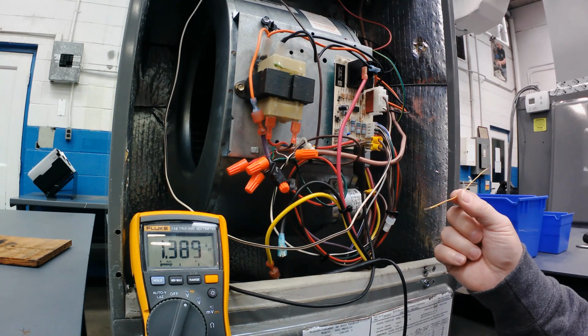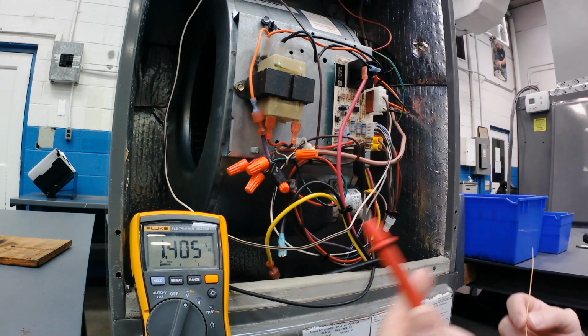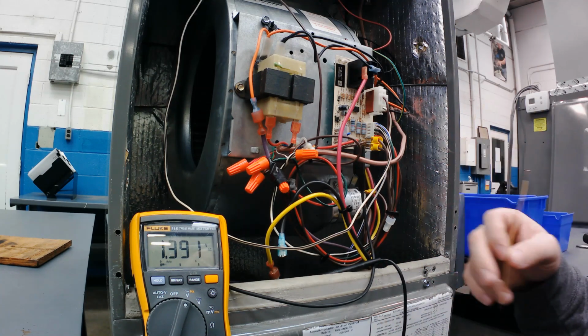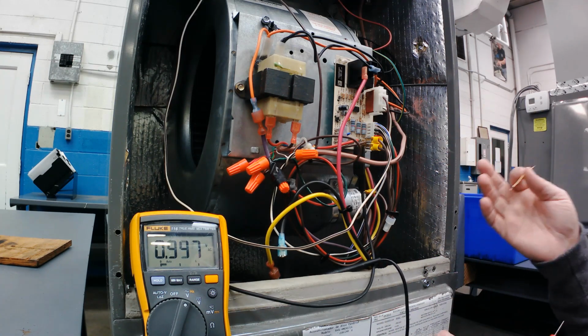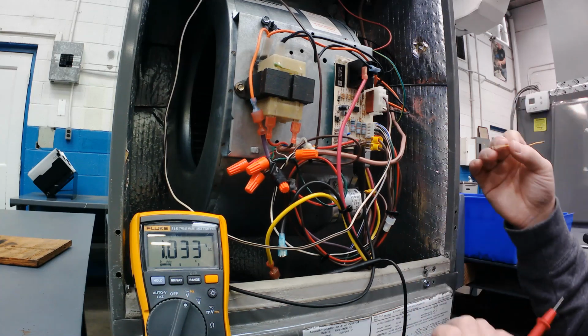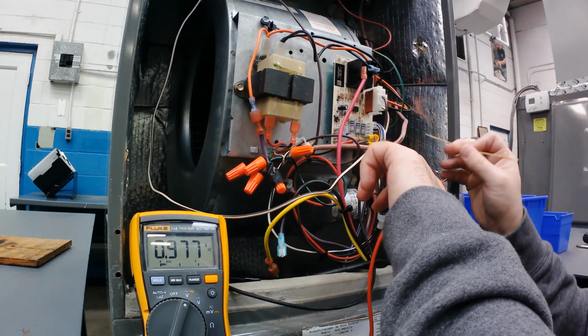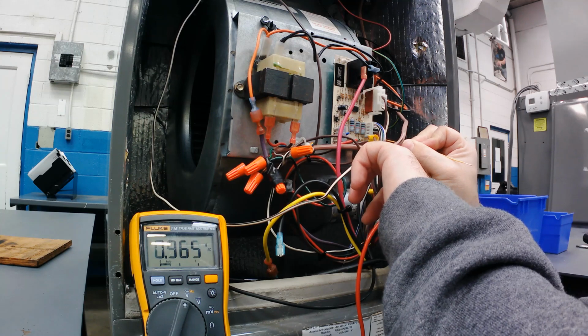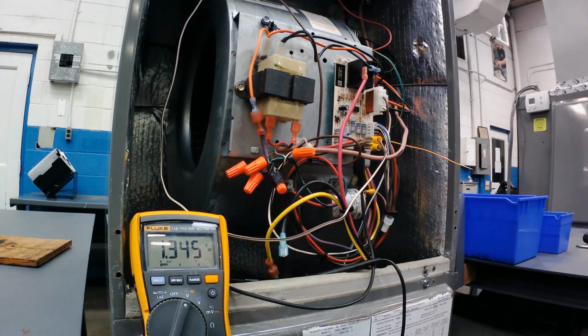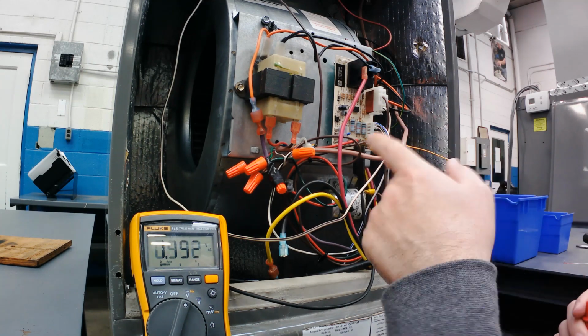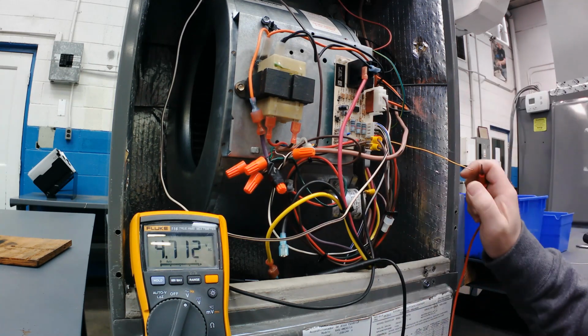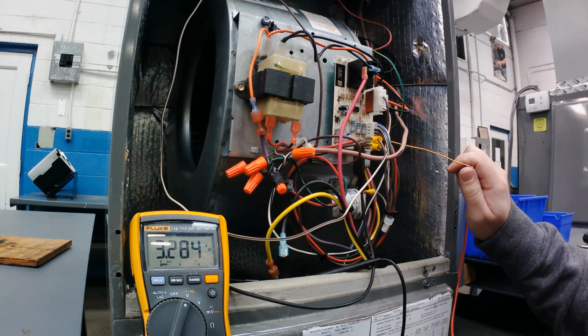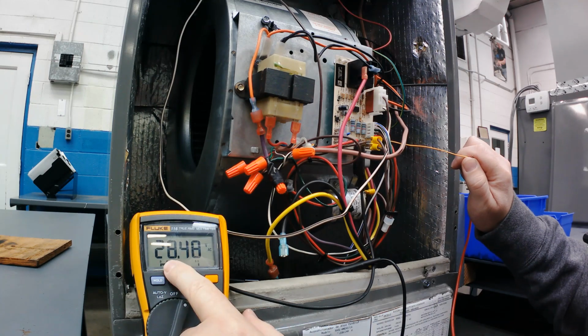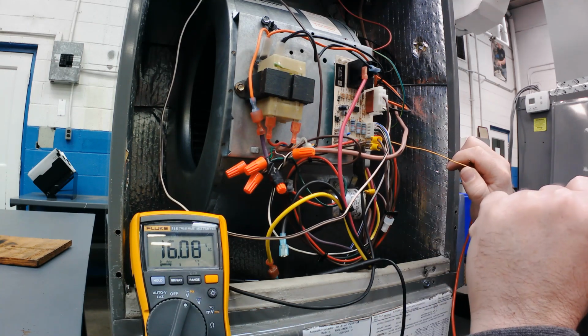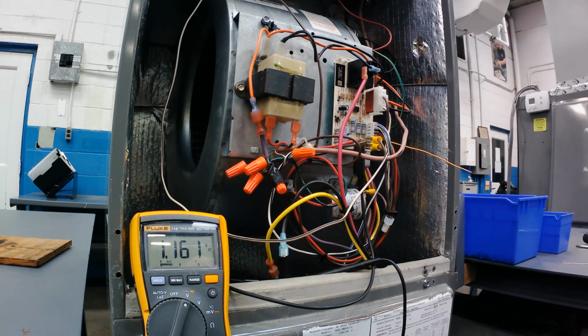So I'm going to take a small piece of thermostat wire. You don't want to jab your lead down in there. You can bend things and inadvertently mess things up, of course by accident. But what I'm going to do is take a piece of thermostat wire, and they make specialty leads like this. I'm going to stick one on R. So if I wanted to see if this board is sending 24 volts out, I would check here, hey, 28 volts. So I know that the board is doing the proper job and sending it to the thermostat.